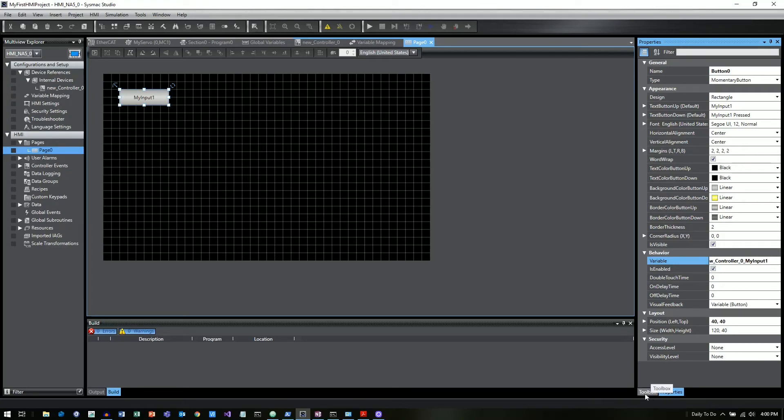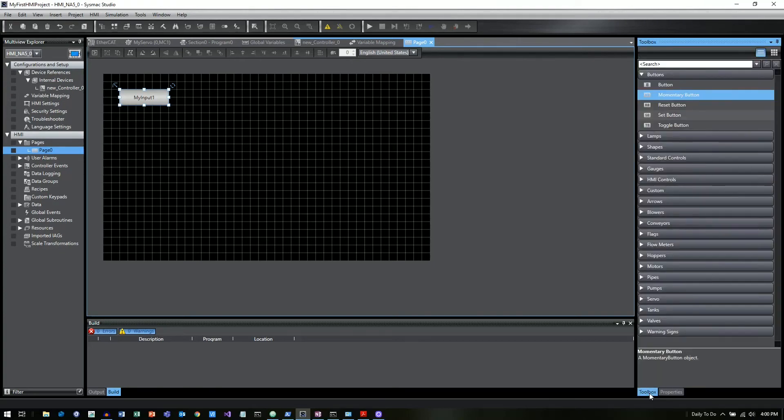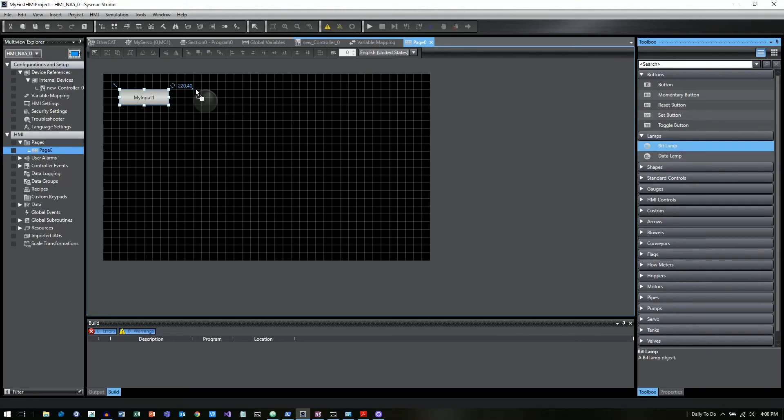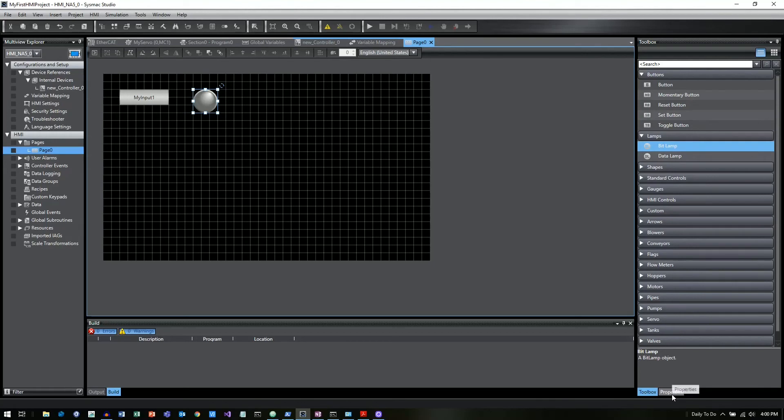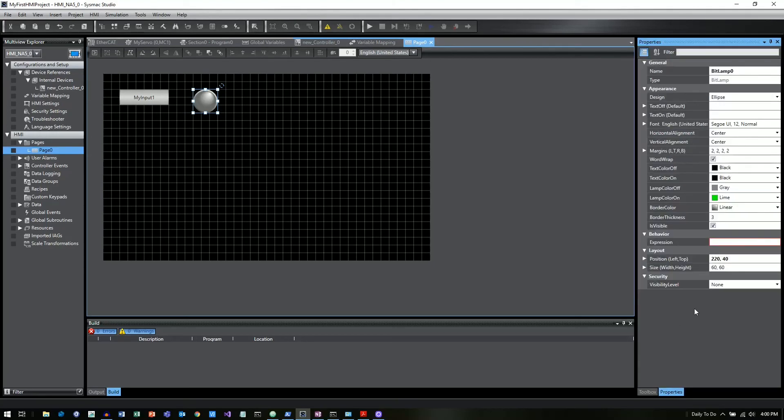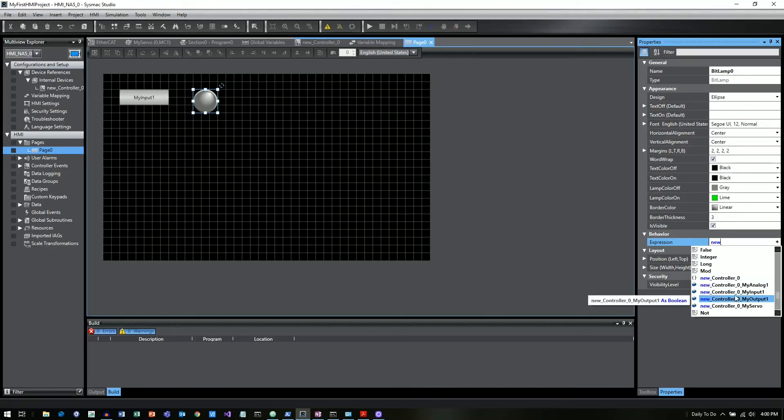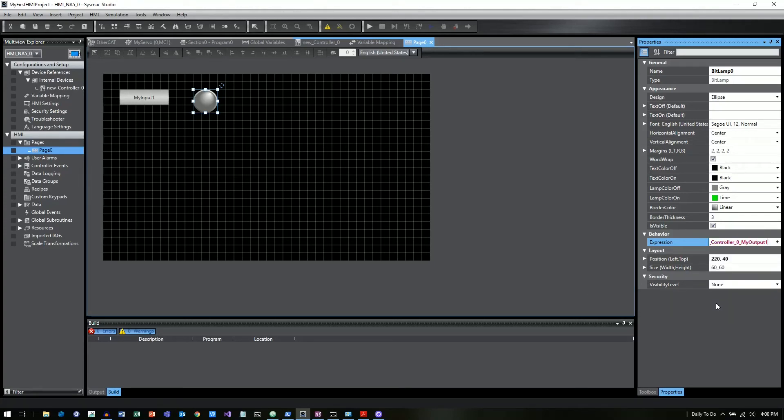And now that has linked MyInput1 to this particular push button on my screen. Let's go back to our toolbox. So if you click down here on the bottom of this right side of the screen, you can see this tab for toolbox. And now instead of buttons, let's click on a bit lamp. And we'll just set this right next to it. And we'll go back here to Properties again. And now we're going to do the same thing. We're going to set the variable. We're going to go new underscore controller. And now we're going to click on MyOutput. And once you have the variable that you want, you can just hit tab and that will autofill the rest of it.